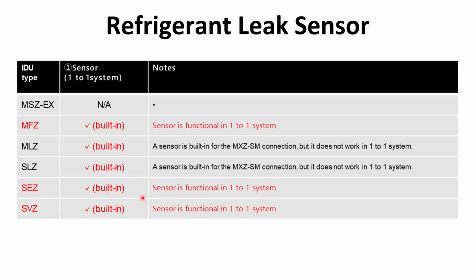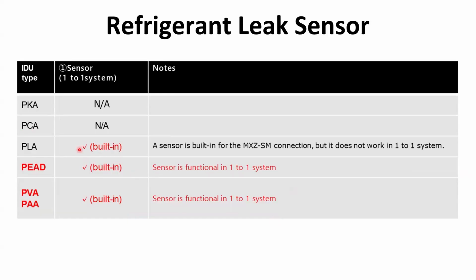SEZ, built-in sensor is functional in a one-to-one system, right? The ducted units, it's going to be functional. SVZ air handler built-in sensor is functional in a one-to-one system. So that's just kind of looking at the M series right there. P series, PKA and PCA units, it's not available in a one-to-one. PLA, built-in sensors built in for the smart multi connection, but does not work in a one-to-one system. And then here's your ducted, right? The PEAD, PVA, and the IntelliHeat coil. So it's functional in a one-to-one system.